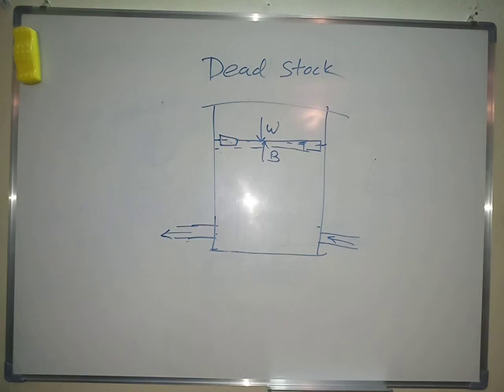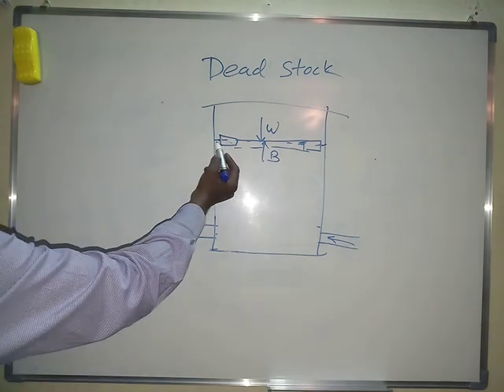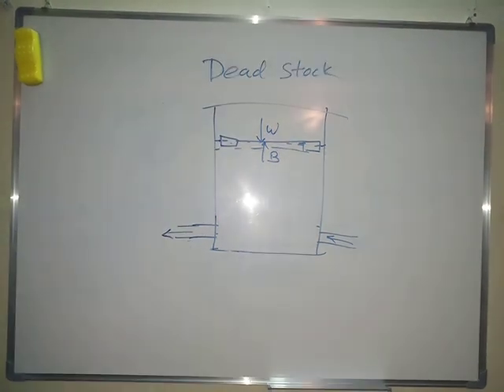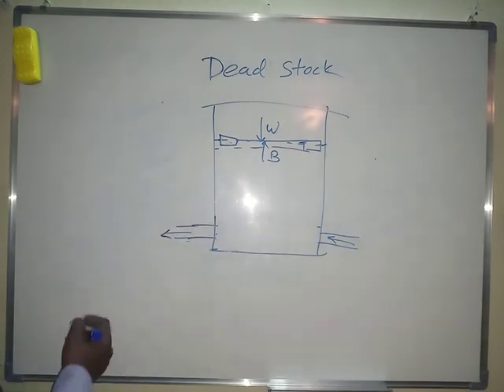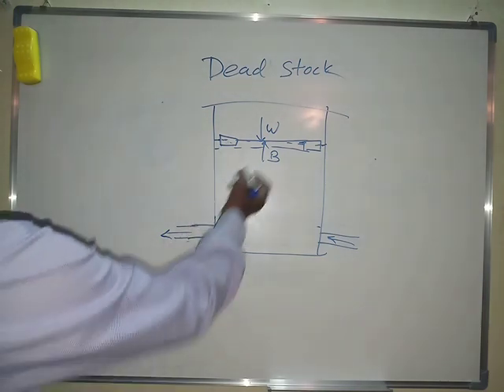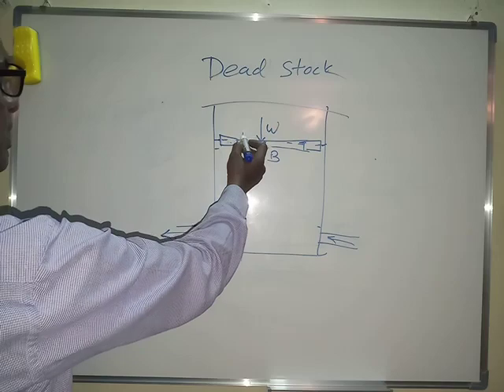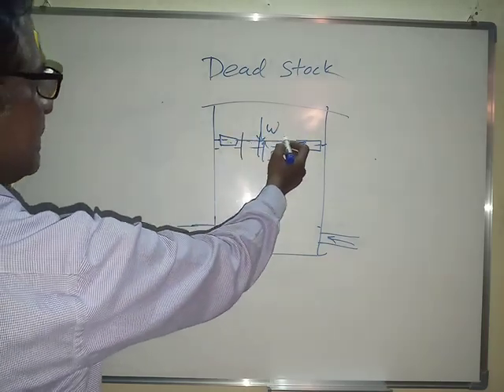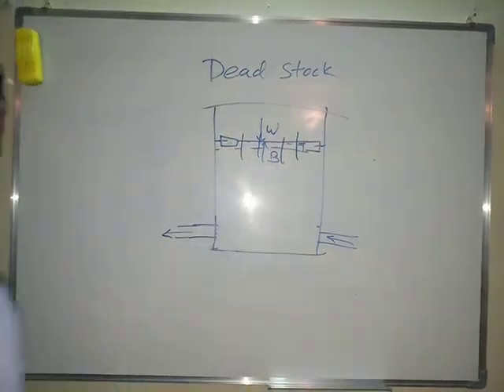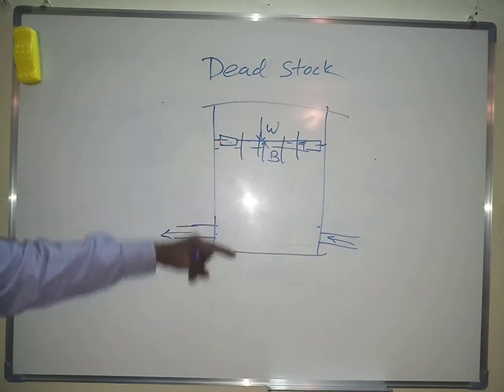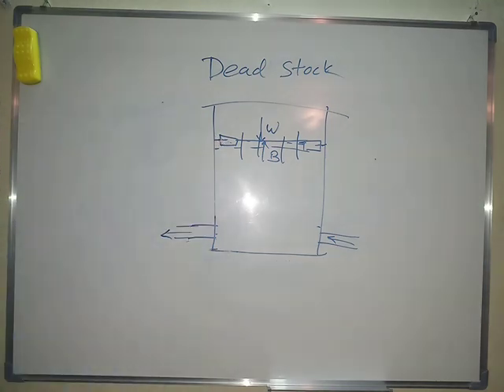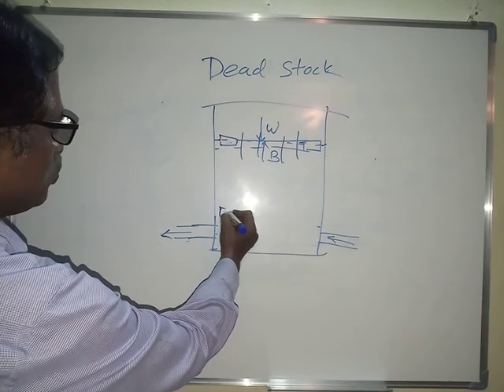I will cover what is the roof correction factor in some other video, but here we are discussing the dead stock level. This floating roof always has legs. So this floating roof will never get settled down on the bottom of the tank. It will have the legs, and when the roof will reach to this level, then the legs will get rest on the bottom plate of the tank.